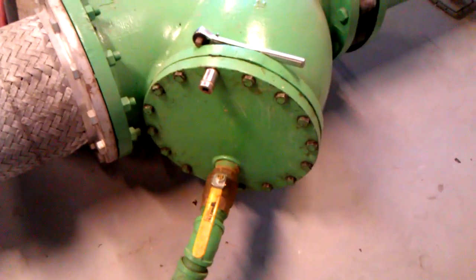Now what you do is shut off the inlet to the one you're going to open. And open the drain. It helps to open the vent on the top of the pump, then the water will really flow out. Oh yeah. You see there's a lot of bolts that go around that plate, and this is how they remove that plate. But I brought in my extra impact wrench from home that I don't use, just so I can take that off in a zip.